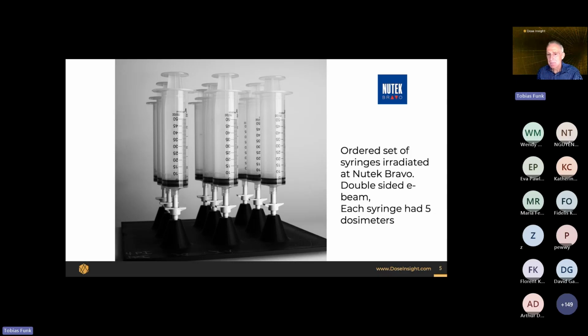So how do we know that these simulations, this modeling, is actually giving us reliable results? The first thing we know is that Monte Carlo simulations have been used over decades in many different fields, and they have shown to be very accurate. And for the sterilization field, we do a lot of cross checks and experiments like the one that I'm introducing here. We took an array of 3x3 syringes. We mounted it on a 3D printed plate to make sure that there's no movement in the packaging.